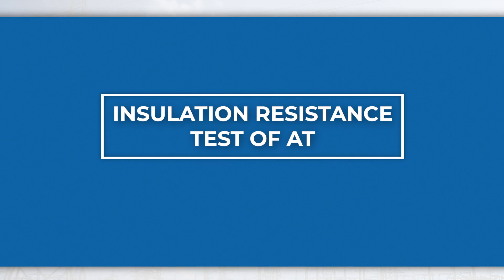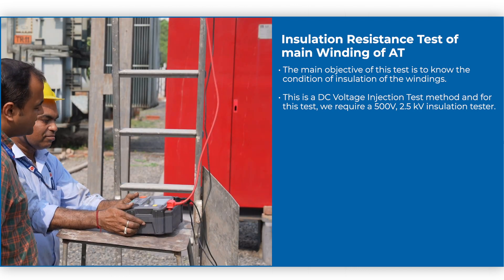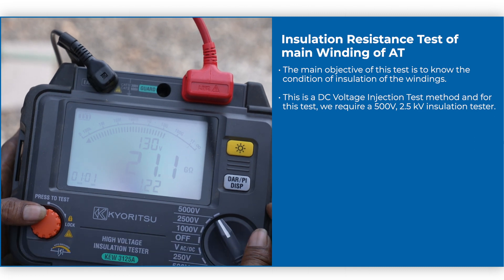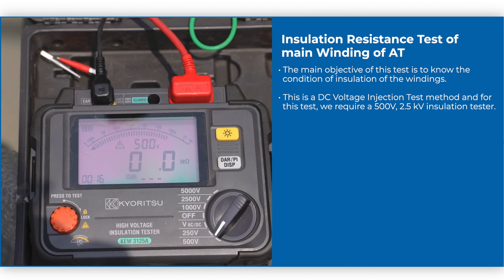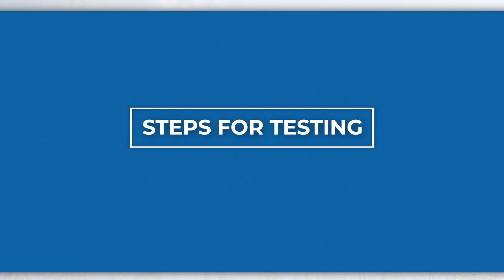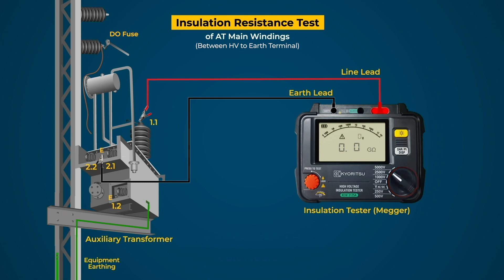Insulation resistance test of AT: The main objective of this test is to know the condition of the insulation of windings of AT. This is a DC voltage injection test method, and for this test we require a 500 volt and 2.5 kV insulation tester. For HV to earthing test, connect the line terminal of the tester to HV and the earth terminal of the tester to earthing. Then check all connections and select the DC voltage level to 2.5 kV on the tester.